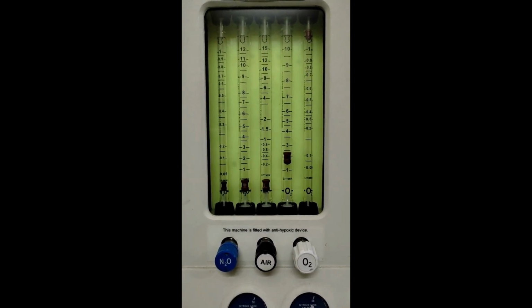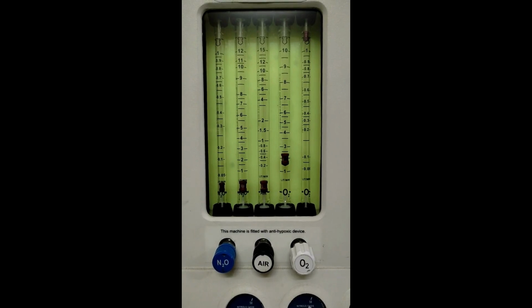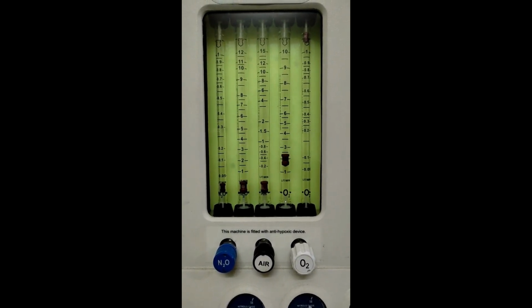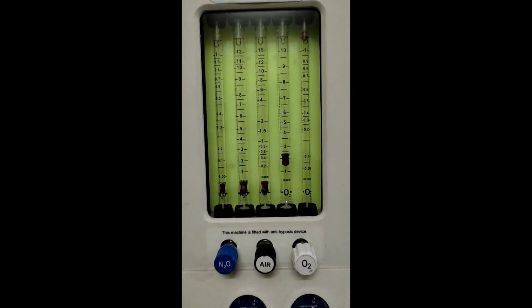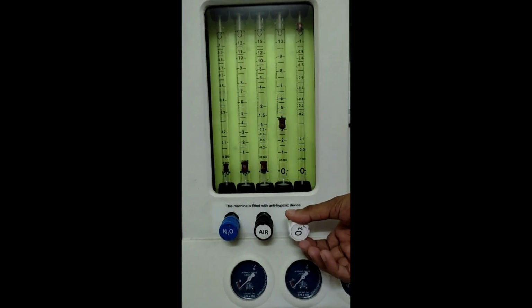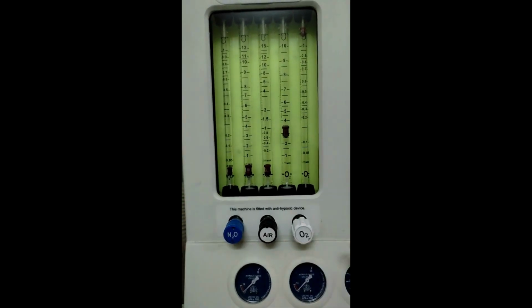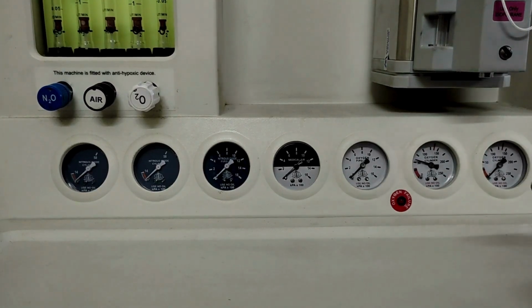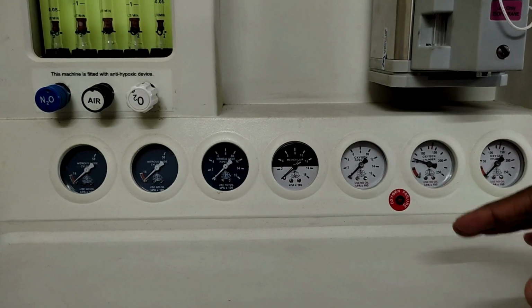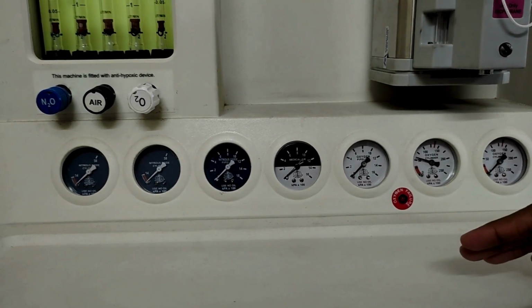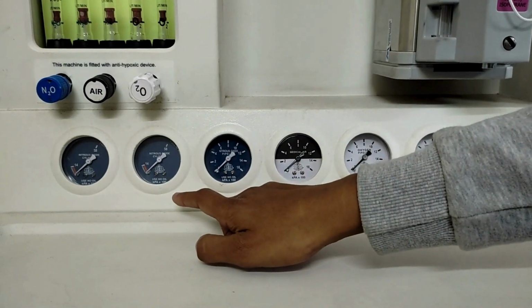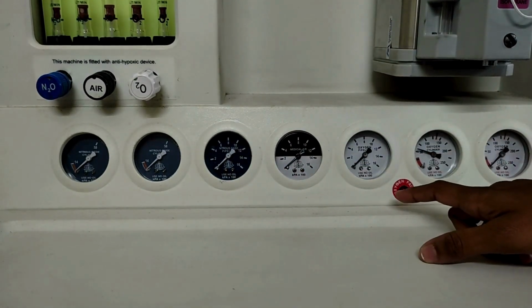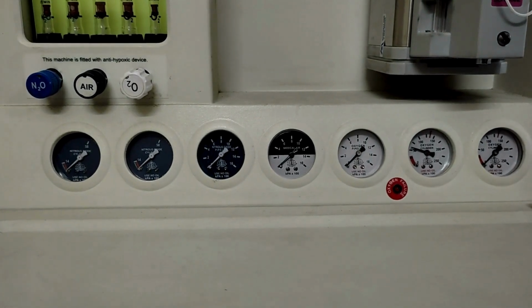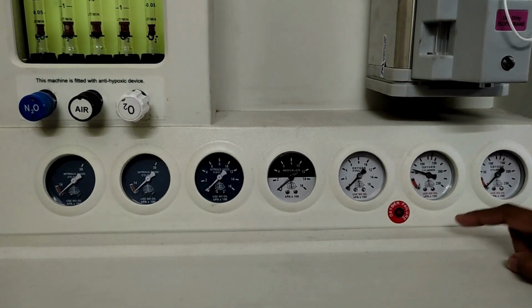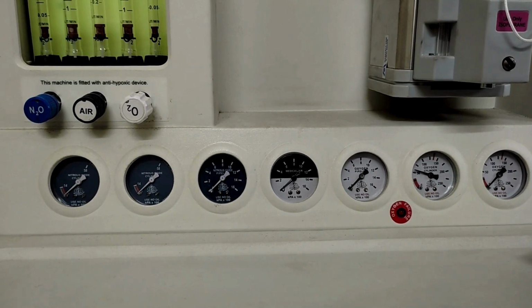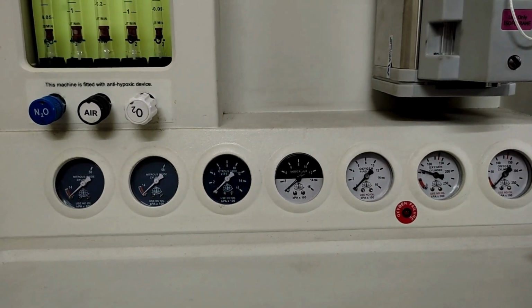The flow meter displays the flow of gas, O2, nitrous oxide and air. The value can be read directly. The unit is liters per minute. Rotate counterclockwise to increase and rotate clockwise to decrease. These are the pressure gauges which measure the cylinder pressure and the pipeline inlet pressures. These 2 are for nitrous oxide cylinders, and these 3 for pipeline inlet pressure, and these 2 for oxygen cylinder pressure. This is the oxygen failure alarm, which gives visual and audible alarms when the oxygen pressure drops below the recommended value.